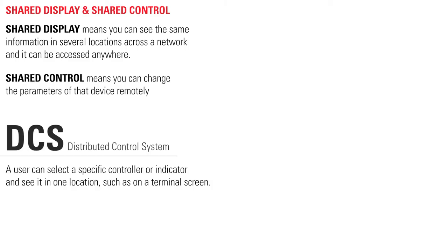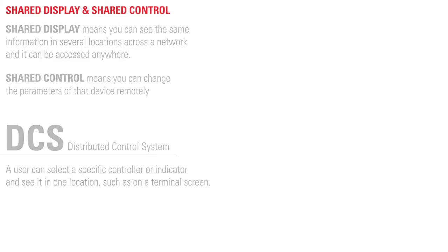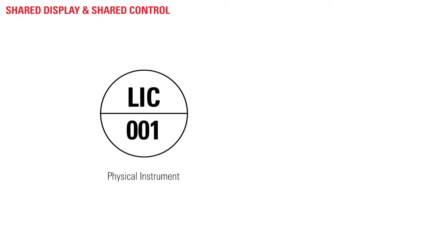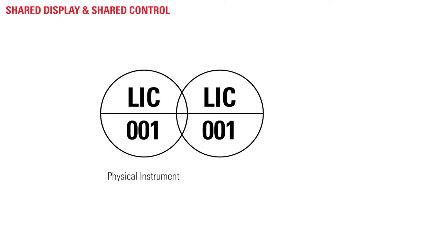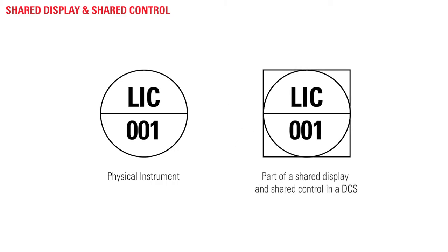With today's computerized systems using virtual controllers like in PLCs and DCSs, new P&ID symbols had to be developed. If you take the same tag number symbol for a physical instrument and add a square around it, it now means that it is part of a shared display and shared control in a DCS.